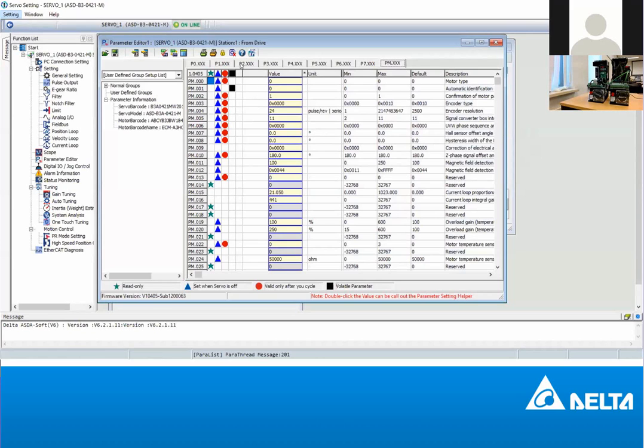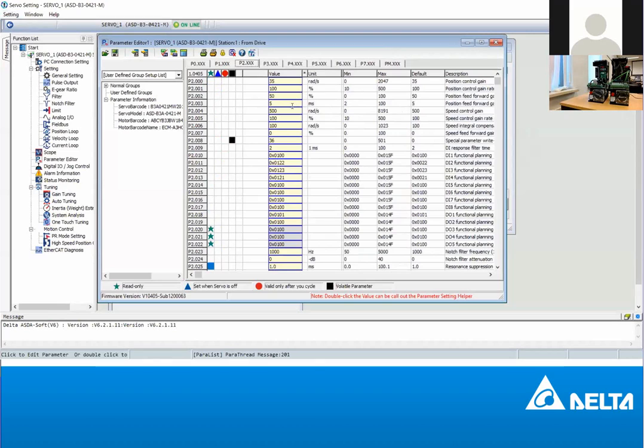So let's go to parameter 2. You click here, parameter 2. We set parameter 2008. So now you can see the value I have here is 36. So we want to write it as 10 to reset it. Also, try to observe the video if there's a response from the digital display. You can see it's busy, done. I hope you saw that. So now it's 10. So we have successfully written.